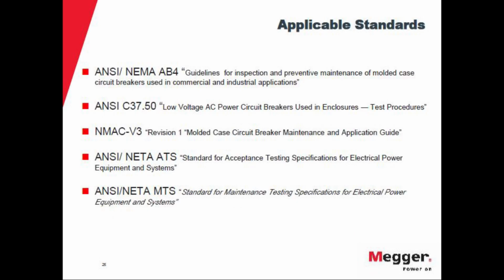Traditionally, all the primary current injection test sets involve a very manual operation. With the instrument that we have now, you can do an automated test. The software that controls the instrument will have the curves for the breaker. So you just look for the breaker in the database, it loads the curve, and the settings are already there for the test.